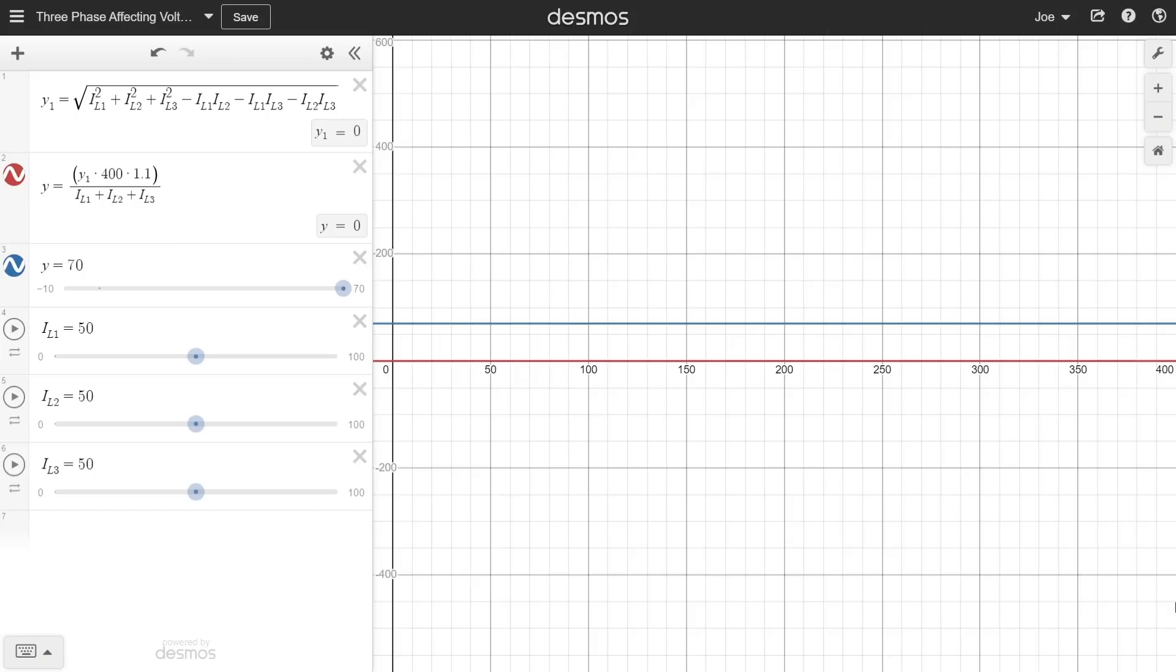However, look what happens when we start to unbalance the system. Let's load up the current in L1 a bit because that's what tends to happen in the real world. Can you see there the voltage between the body of the car and the literal earth is now going up, until if the difference in the phases gets big enough it goes over that threshold value of 70 volts and suddenly the person touching the car and standing on the ground has 70 volts across them and is in serious danger.